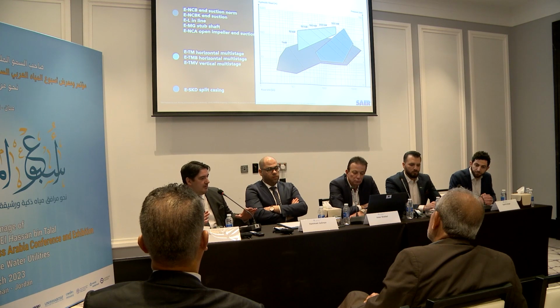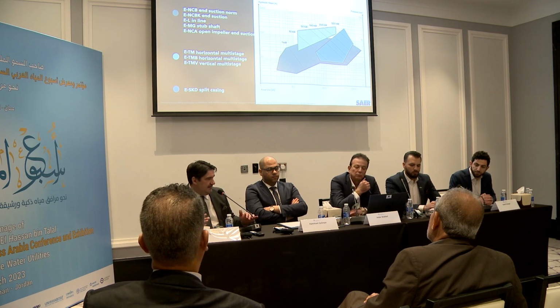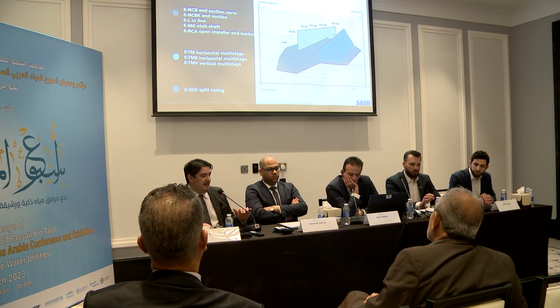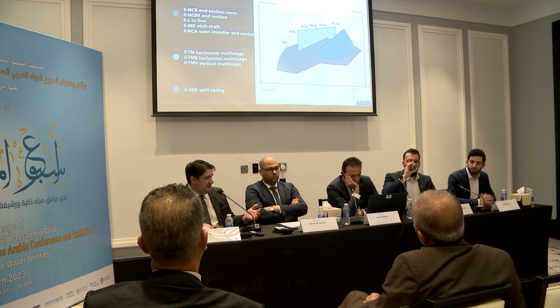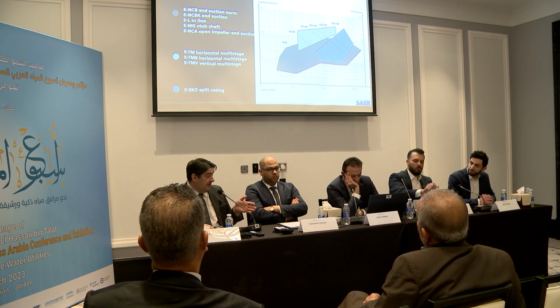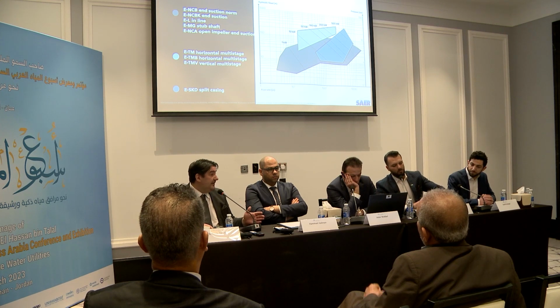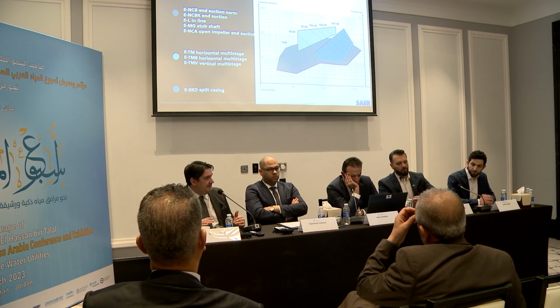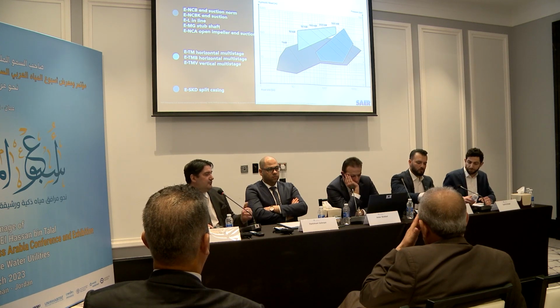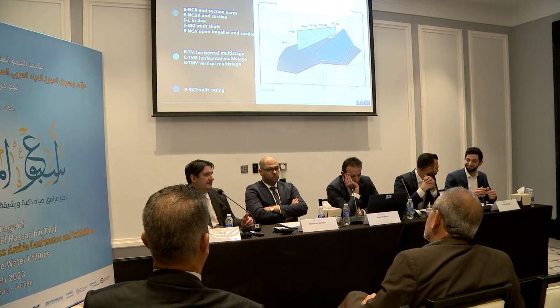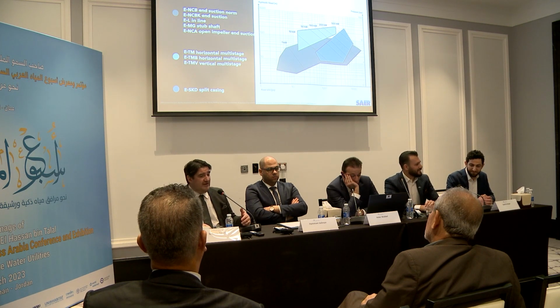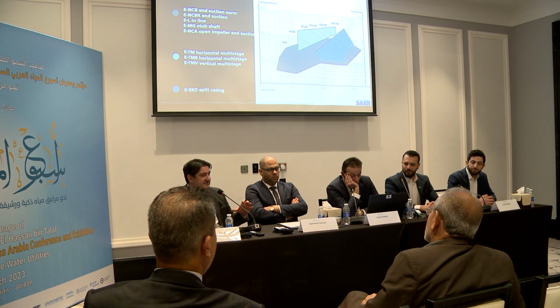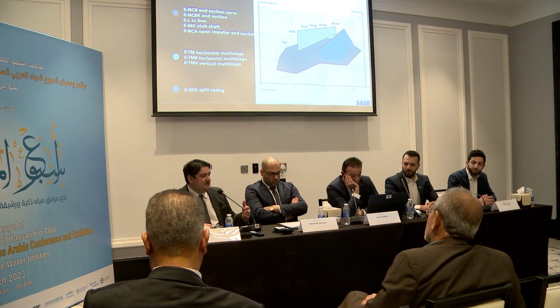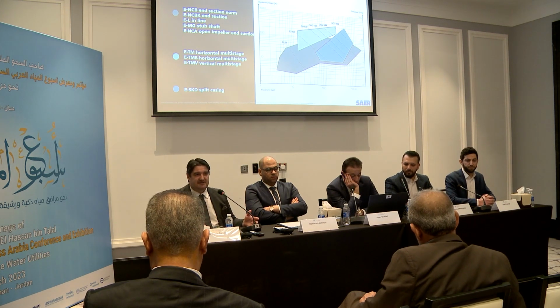The range of flow rate and head is very variable. So with our actual range of pump as turbine, we can cover really high flow rates, up to 1,000 liters per second, but also starting from really small flow rates of a few liters per second. The difference of head is between 8-10 meters up to 300-400 meters. Which pump can be used, single stage or multi-stage, or which type of execution, is related to the available flow rate, piping size, and the difference of head.